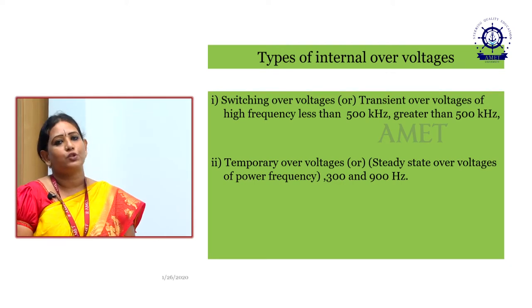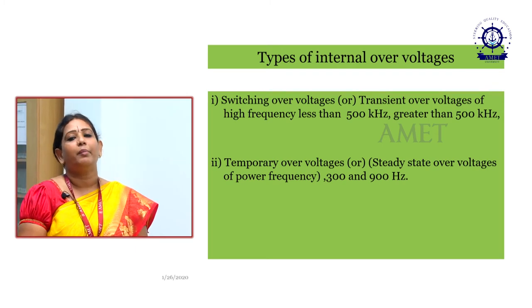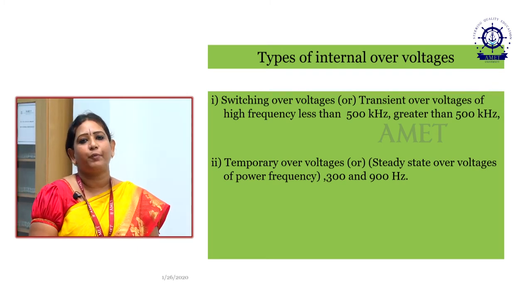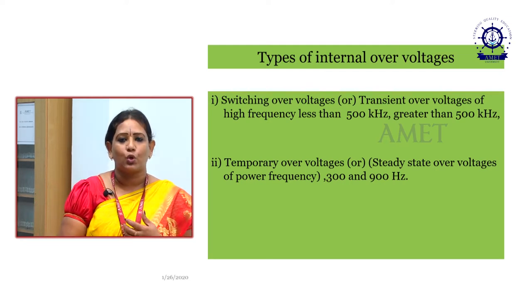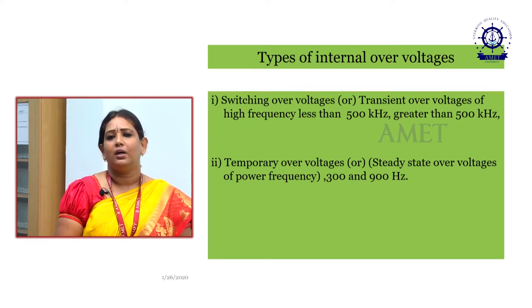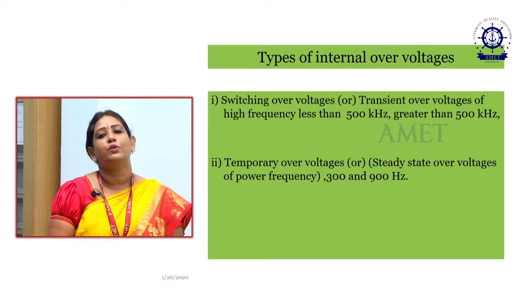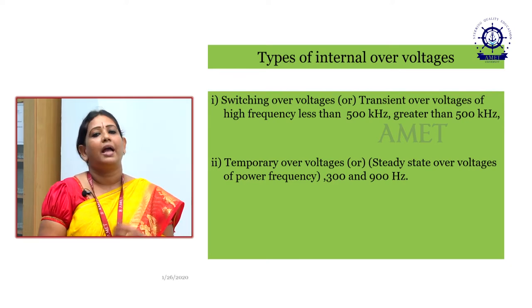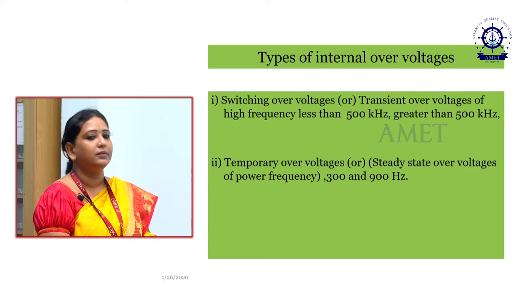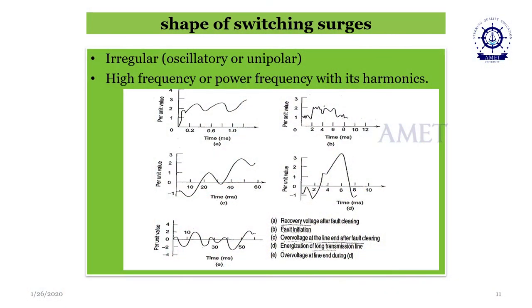Anyhow, these have to be taken care of, and remedial actions have to be taken to restore from these types of internal overvoltages. If it persists or if action is not taken, it leads to a very dangerous and hazardous situation for the entire power system network, and an imbalance in the structure may occur. Look at the shape of switching surges. From the name, we know very clearly, it is called switching.